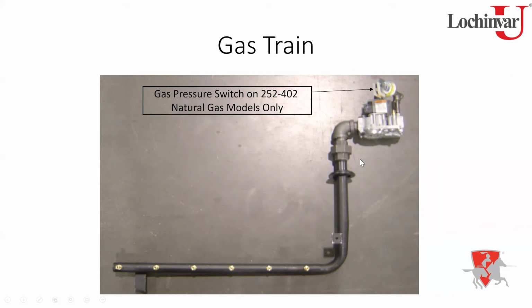So if you ever are dealing with nuisance air pressure switch lockouts, low air lockouts, make sure that thing is sealed. Something else, don't take a screwdriver and start to poke down on it or anything, because at that point you're probably going to puncture it. I just generally use my hands to kind of clip it in place. It generally isn't too hard of a thing to do. So again, air pressure switch issues, that's one thing to check. And just make sure those orifices are good and clean when you do your annual.